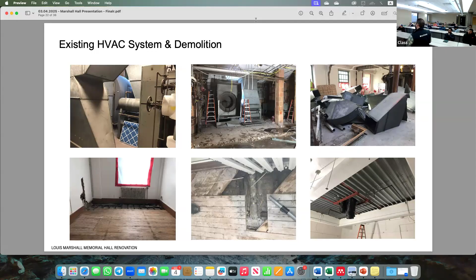There were some fire code updates done in the 90s, but that was mostly stairwells and things like that. So we were dealing with almost competing systems in the existing building - RTUs, hot water heaters underneath windows, and these gigantic air handling units on the 4th floor, the basement, and a couple other spaces. They were providing too much air in spaces close to them and not nearly enough air to spaces further down the line - toward the end, which is what Quinn was talking about with the VRF system. It wasn't meant to heat or cool the whole building, just those spaces at the end of the system.